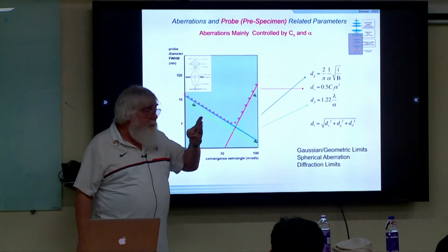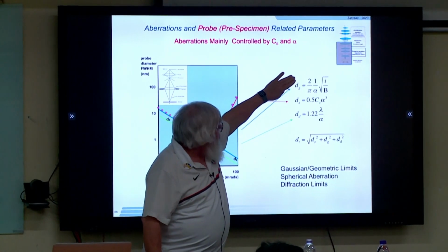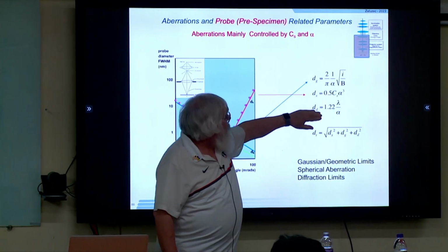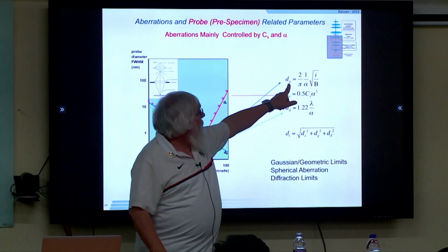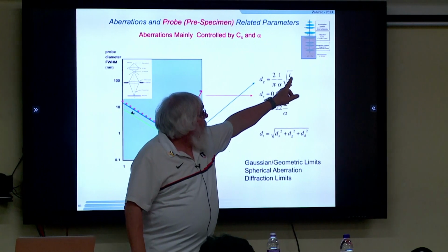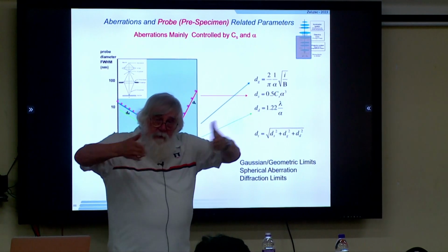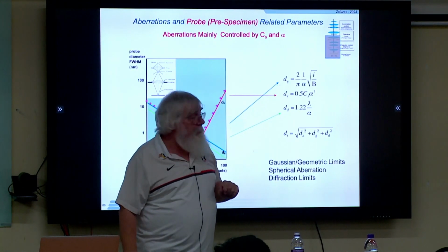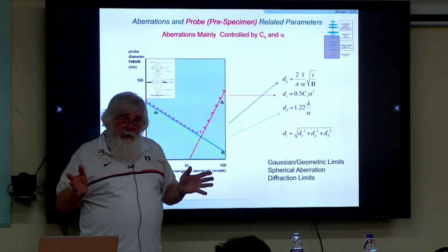three limiting factors. There is the diffraction limit, the brightness of the gun, the spherical aberration, and the diffraction limit, okay? So one of which is how small of a probe can we form? It's called a Gaussian probe, D sub G. And that's related to the amount of current you want, the brightness of the gun, and that convergence angle that we did. So that's one fundamental limit. You can't change that.